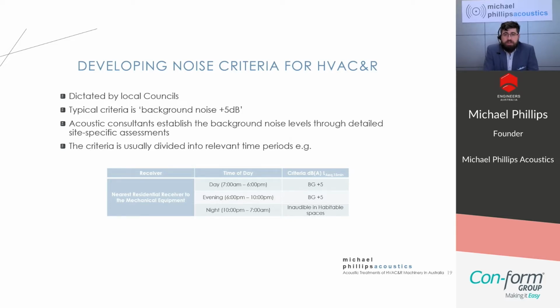Okay, so let's talk a little bit now about how we develop the noise criteria for HVAC&R. This is usually dictated by local councils. The reason that it's there is to ensure that noise levels at the nearest noise sensitive receivers are reasonable and undisturbed by any potential intrusive noise sources. Typical criteria that we would see is background noise +5 decibels. And we now know that 5 decibels is readily perceptible noise, which we could consider to be reasonable.